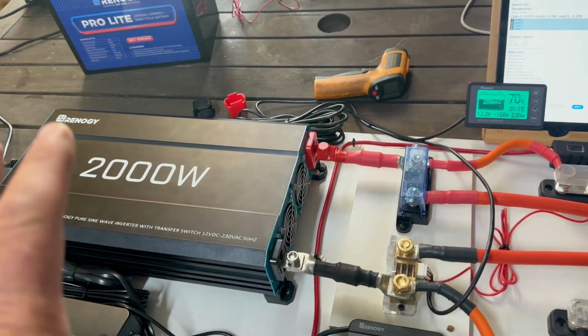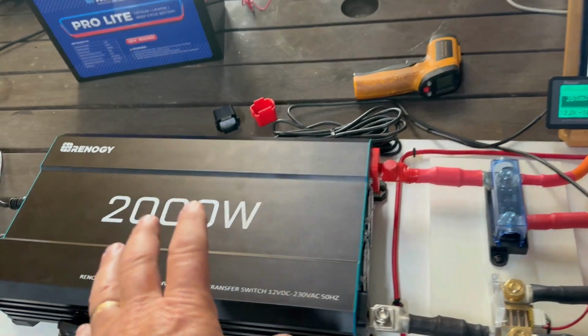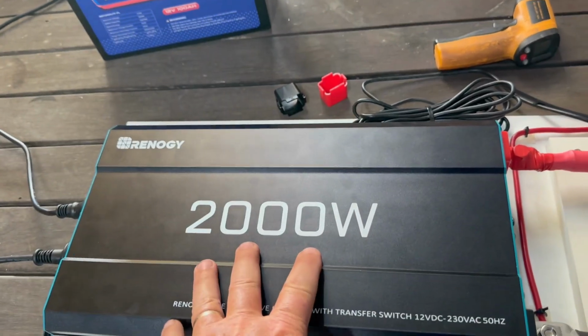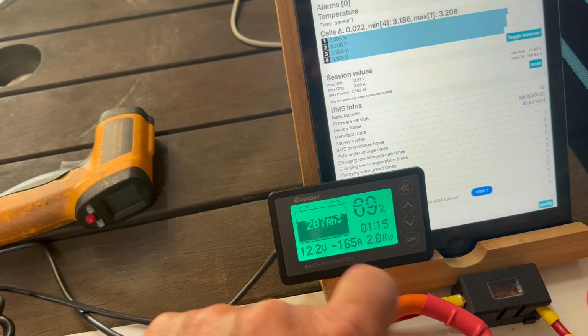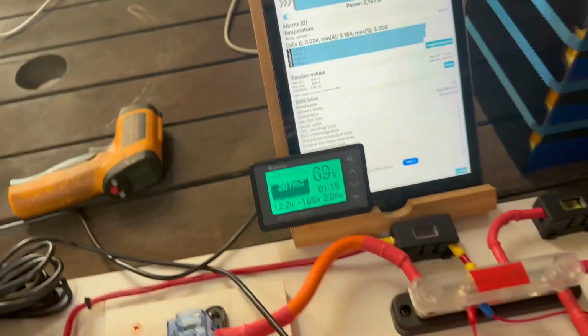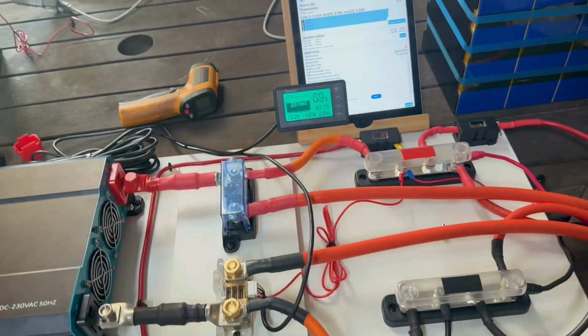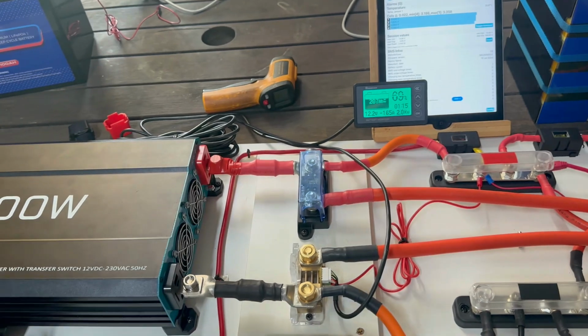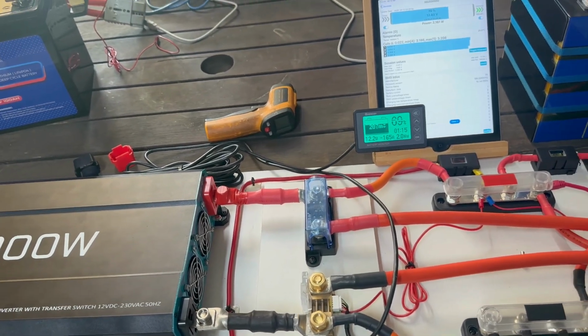So just remember guys, if you're going to run the full capacity of this inverter, you're going to need something that can do 165 amps continuous. In my mind, you need a 200 amp BMS with a minimum of a 200 amp battery.